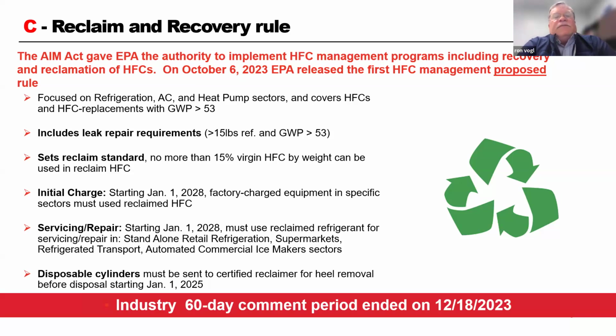One other thing on the EPA's push, they really want to get focused on recovery, and some other things that they've put in place. These are proposed here that you're looking at on the screen. In the past, if you had larger charge size and leaks, and in California, again, I don't want to plead too much ignorance, but on the federal level now, if you've got a GWP greater than 53 and you've got 15 pounds or greater, then you have to start following the leak protocol, record keeping, etc. It's proposed. That brings you into the realm of some rooftops, and the rest of it, where typically in the past, grocery stores and cold storage had to do that kind of record keeping.